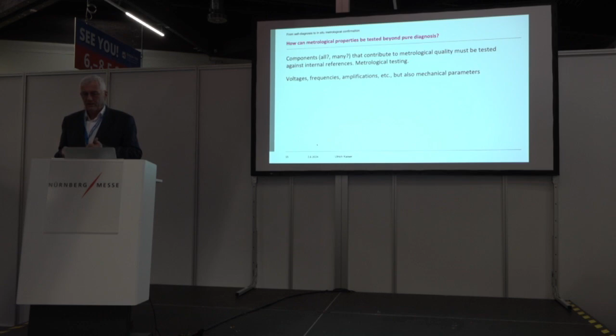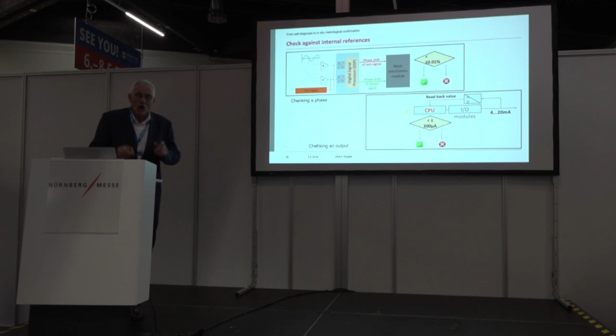When you want to check a clock, you need a second clock. And when the clocks are different, you can say there's something out of order. Second, for example with these flow sensors, they measure a phase shift. You create a phase shift virtually and then check whether the electronics is still working the same. You have also an internal reference. Another example: you have an amplifier and you measure back what is coming out and check it. That means all that quantitatively contributes to calibration behavior, calibration performance, you check explicitly. But this is important: not all components, only the components which are accessible for that.